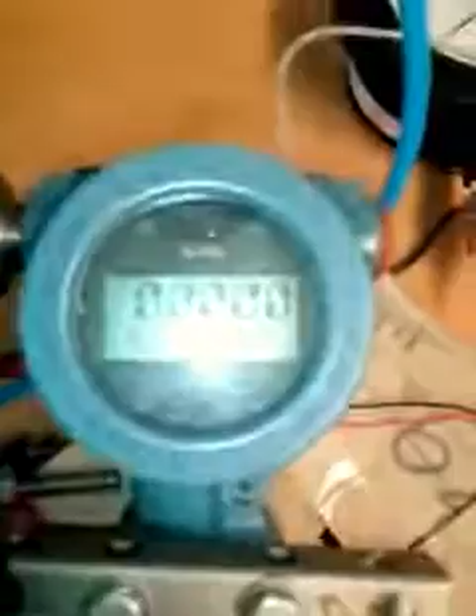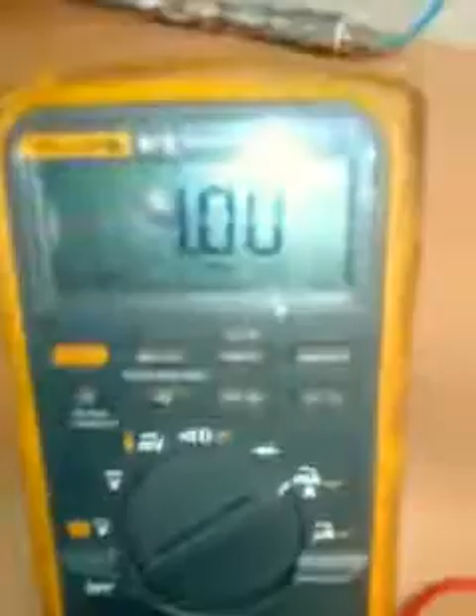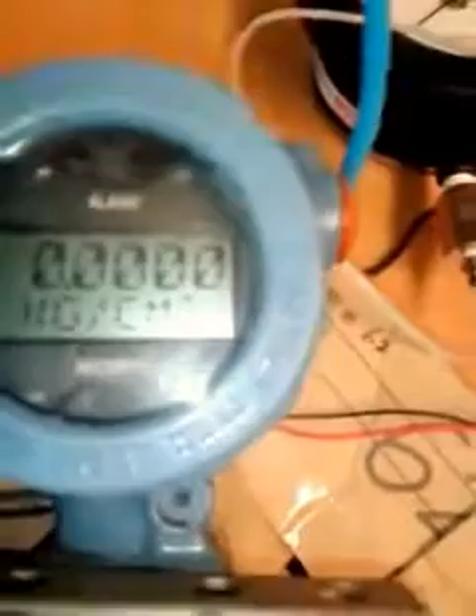Okay, look at the value. It will suddenly change to 0. Yeah, that's right. See? So the value now, the display is 0, 0, 0, and the corresponding current is the same as the ideal. The computed value is 4 milliamp, and it should be. If we apply the maximum pressure as the URV set, 250 kg, the milliamp will be 20 milliamp.